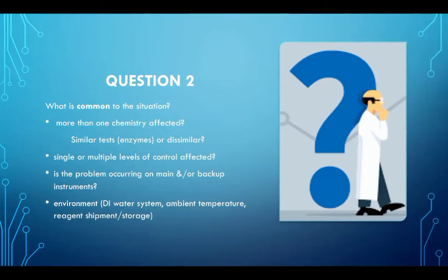an environmental factor, that is your deionized water system, or maybe temperature, or you have received 4 reagents in a single shipment and all 4 of these reagents are showing problems, or you have multiple refrigerators, and in a particular refrigerator you have stored these 4 reagents or 2 reagents and these are showing problems. So that way we have to develop a little Sherlock Holmes within us.